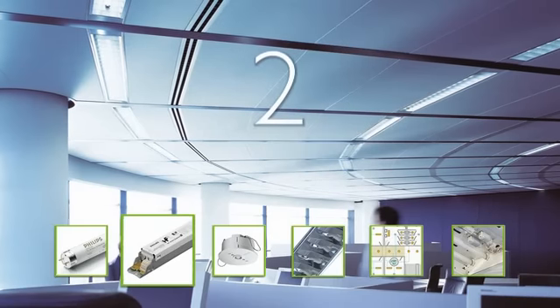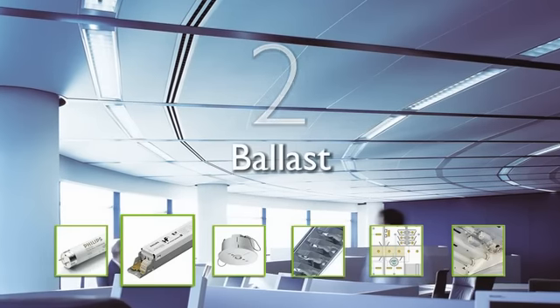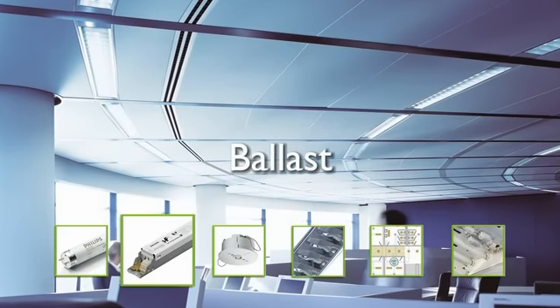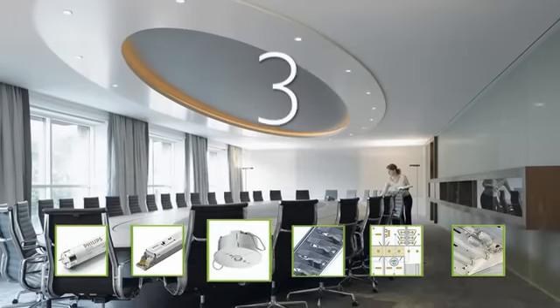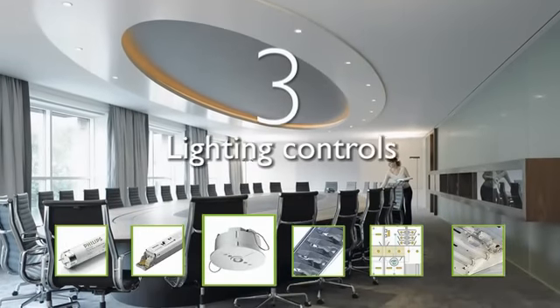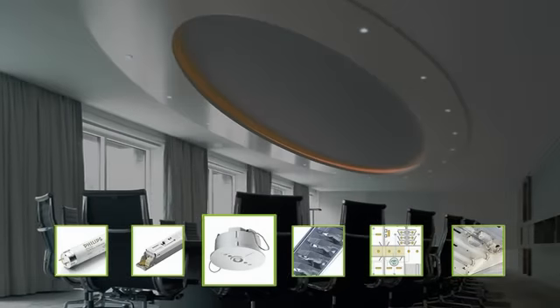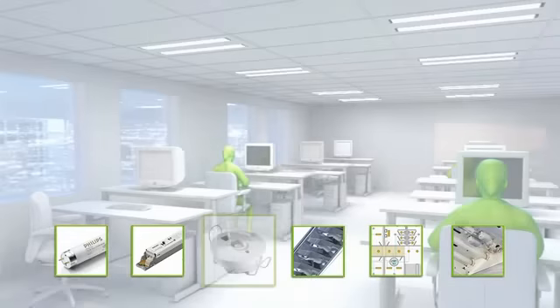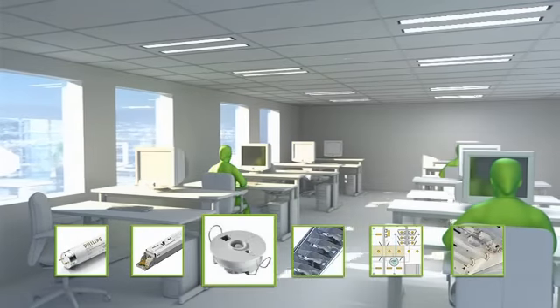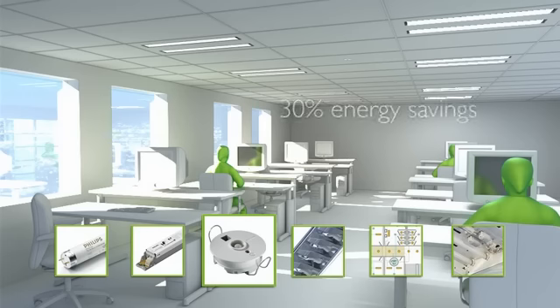The second relevant factor is the ballast. Switching from traditional electromagnetic ballasts to new electronic ballasts will save up to 25%. The third factor is the use of lighting controls. These are simple devices which turn off or dim down the lighting when people are no longer present, saving up to 30%. Other controls can dim the light when enough natural daylight is present, which offers additional energy savings of up to 30%.